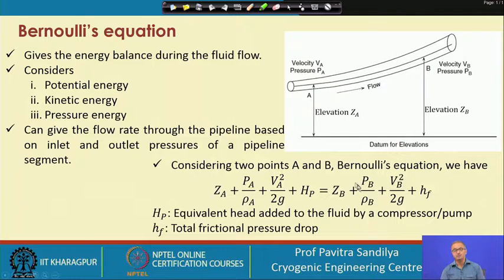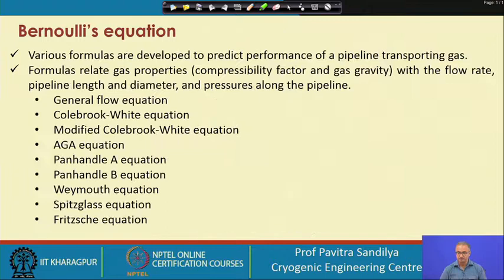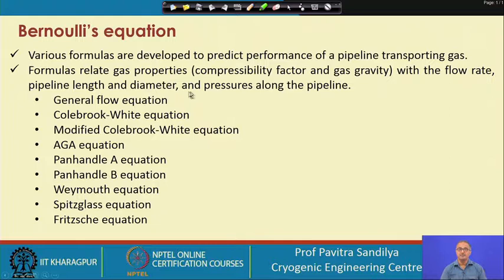Writing the Bernoulli's equation: the first term signifies potential head, the next is pressure head, the next is kinetic head, and H_P is the equivalent head added to the fluid by the compressor. On the outlet side we again have potential head, pressure head, kinetic head, and the frictional losses during flow. This energy balance equation is used repeatedly to find out the pressure loss in the pipeline. Various formulas developed from Bernoulli's equation use gas properties like compressibility factor, gas gravity, flow rate, pipeline length, diameter, and pressure along the pipeline.